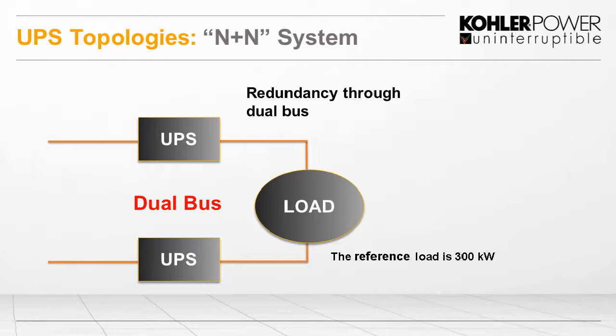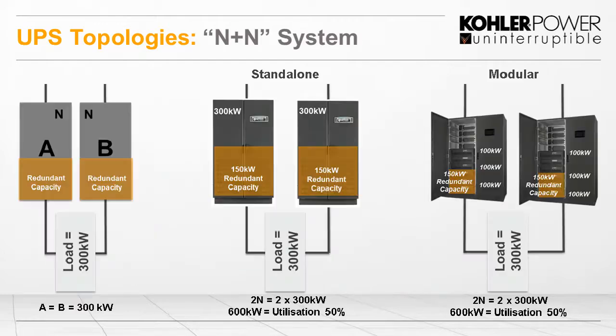So an N plus N system is what it says. We've got an N on side A and an N on side B. So we have redundancy. If one UPS was lost, the other UPS would be supplying the load. So again, there are different ways of doing that. We can have two standalones, each feeding each side of the load, or we can make it up out of smaller modules, allowing expansion and flexibility. But each one in this case has got to have 300 kilowatts on each side.